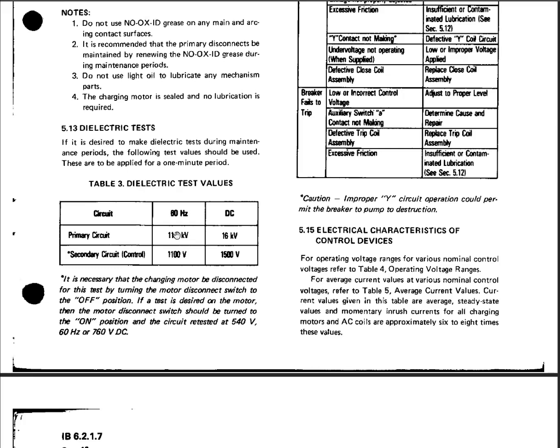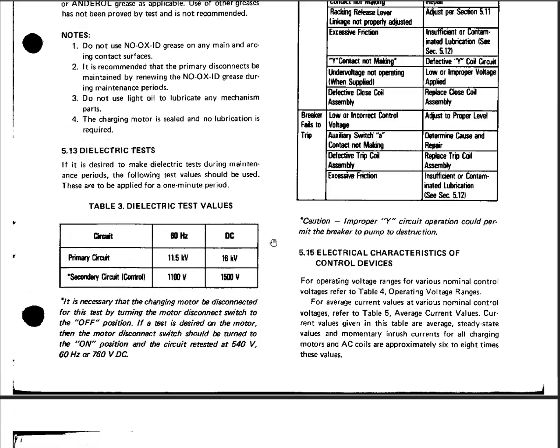So don't use the MTS, use the manufacturer's literature, and it's what NETA tells you to do in the first place. So you should be doing what the book tells you. Otherwise, you're not performing the test properly. If I see your test report, I'll call you out on it, and I'd expect anyone to call you out for not performing it according to manufacturer specification. By the way, this book isn't too hard to get, I just Googled it. So this is the high pot.